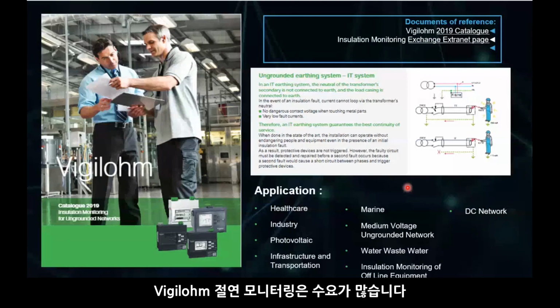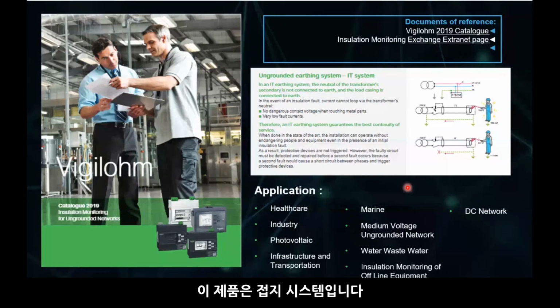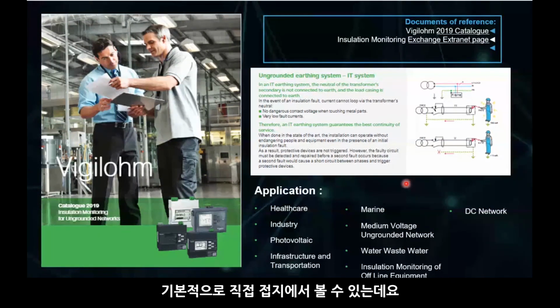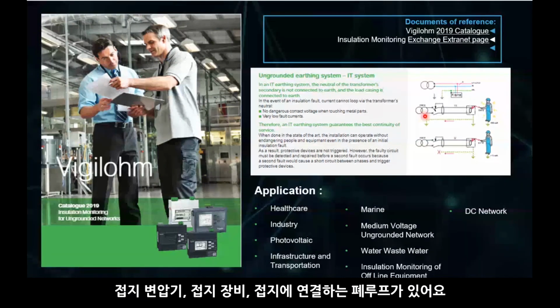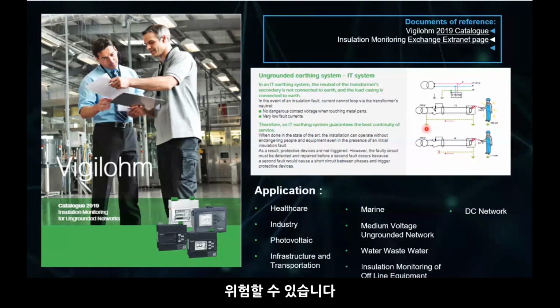So Vigilohm installation monitoring - a lot of people will ask where do we sell this offer. This is purely an ungrounded earthing system, we call it IT systems. In a really solid grounding system, you have a transformer that's grounded, equipment that's grounded, and a closed loop that goes to ground. This is very dangerous.